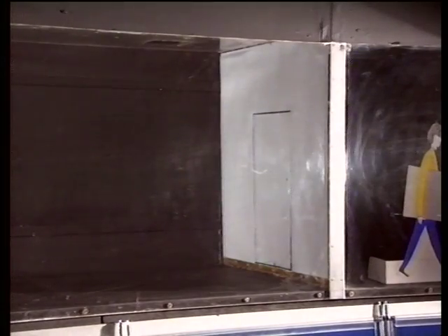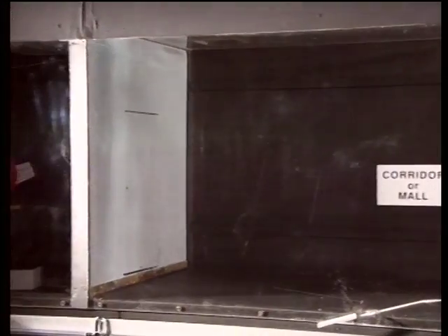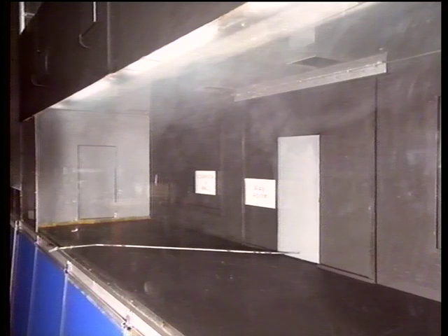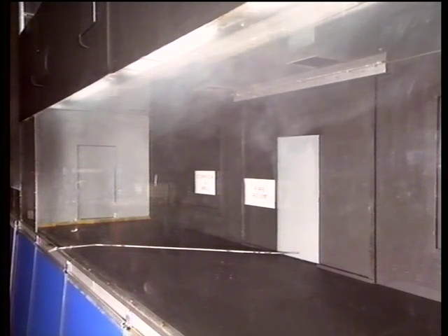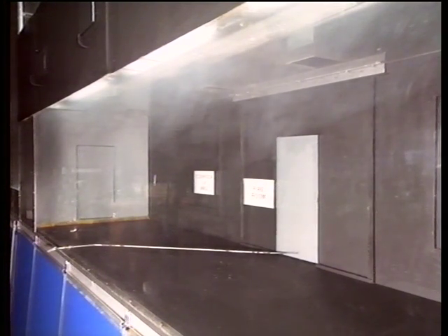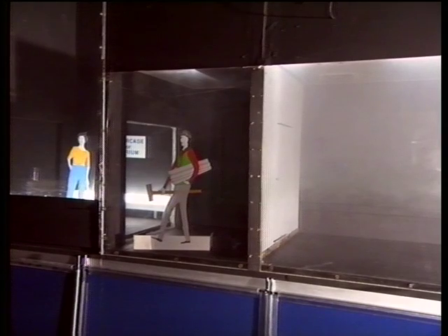Well, what we can do is use what's called a compartmented type smoke control method. This is where we introduce partitions every so many meters down the corridor. And these partitions contain the doorways through which people are able to leave and enter the corridor. As the smoke starts to develop again, it comes up to these partitions, the smoke is stopped and it's contained within the locality of this part of the building.